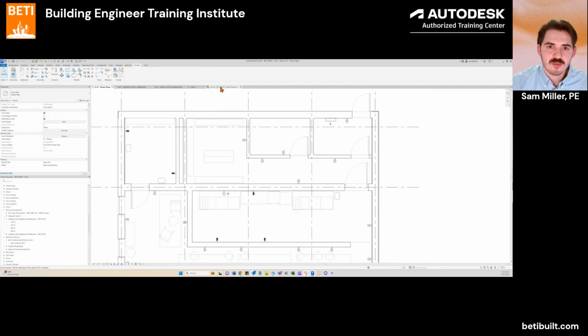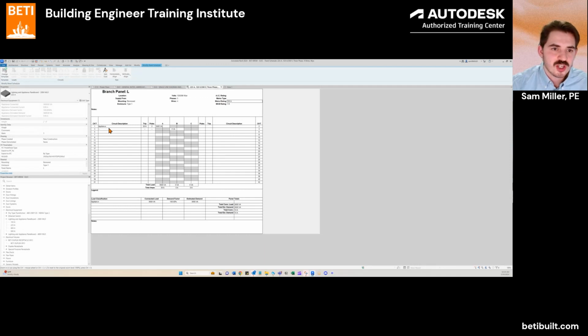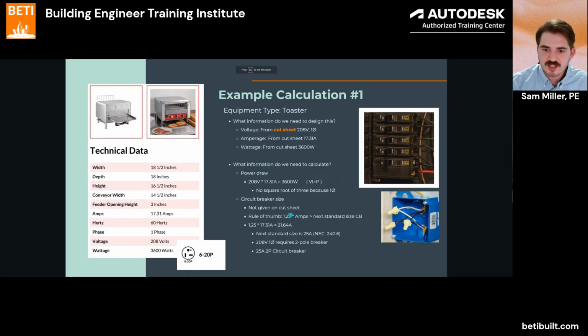And then if we go back to my panel schedule, you'll see where this circuit now has come up onto the branch panel. So you can click in here, you can rename it to toaster. And then this brings us to the topic of circuit breaker sizing. This is the standard rule of thumb to size your circuit breaker. So if we didn't have the power, it'll walk you through how to get that from amperage. And then it will show you the circuit breaker size.